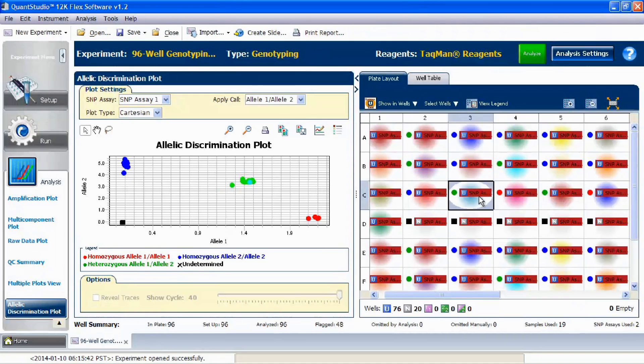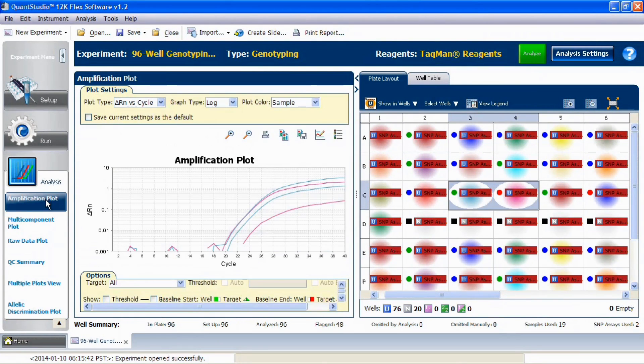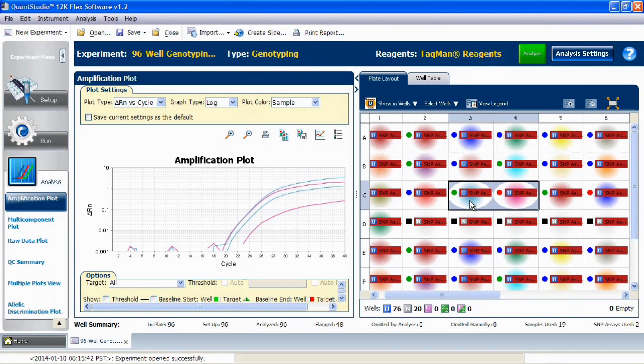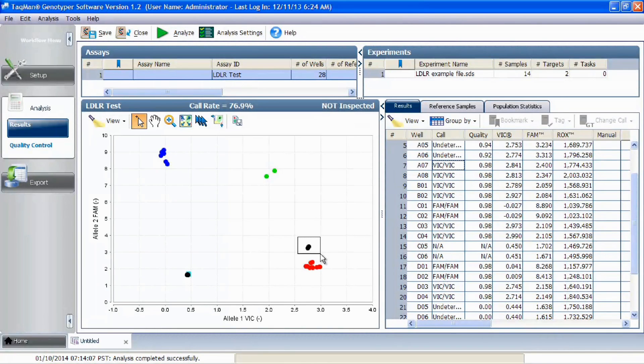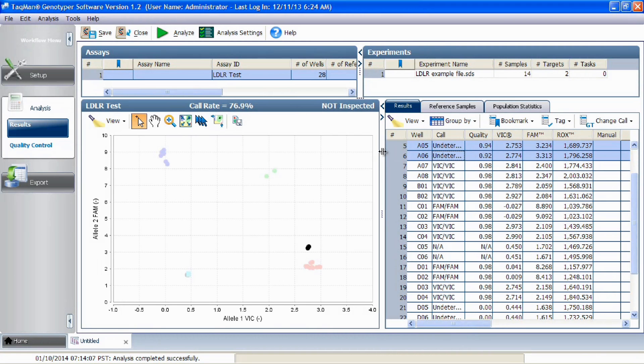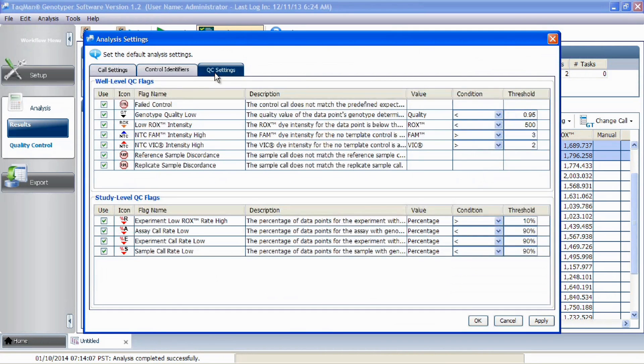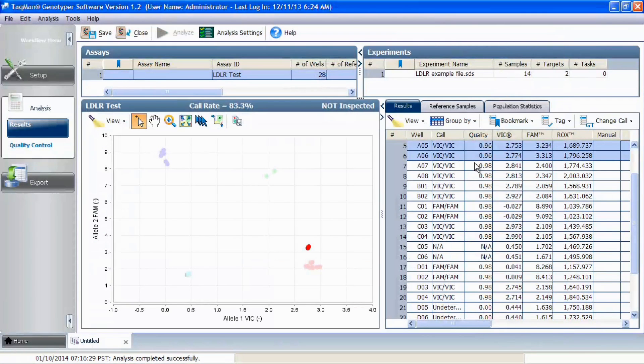The software makes calls based on the dye ratios and cluster orientation, and not the CT values. There is no traditional threshold to be used. If we look at two respective samples, we can see there is a difference in the amount of VIC amplification, so even though there can be some mismatch binding, we can still differentiate the clusters. Instead of a threshold, a quality value — which is the probability of a genotype call — is assigned to each well. Most software sets the default value at 95%, but you can adjust it manually. A data point with a quality value lower than the default threshold does not pass quality specification and will be an undetermined call. By lowering the default threshold, you may change an undetermined call to a genotype call. Running a no-template control sample is also helpful for proper calls to be made.